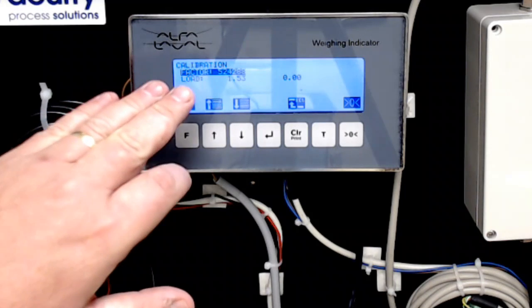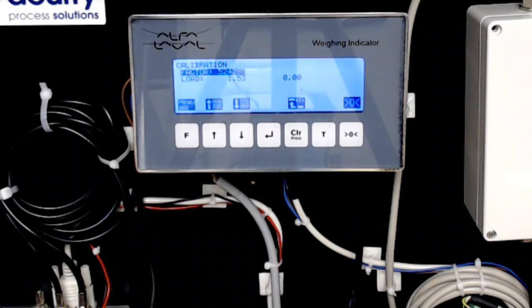And it's important to know, when I'm in this calibration screen, that number that you see there, 524,288, is the standard calibration factor that is on every single load cell system that Alfa Laval ships. So it's important to understand that that's the basic number that we start with. When you do a calibration to that system, and we'll go through it in a moment, that number will likely change if the system isn't 100% accurately calibrated. I can either do a calibration process or I can force that number to change without going through a calibration process, although that's not very common.